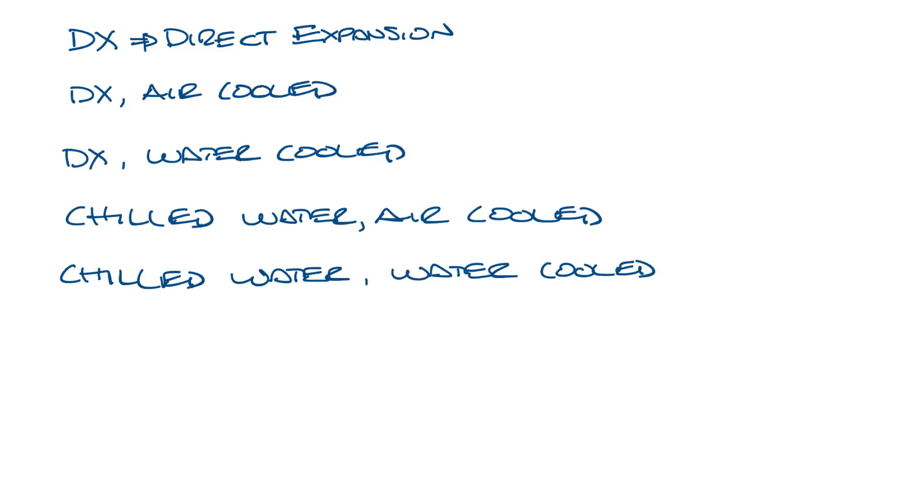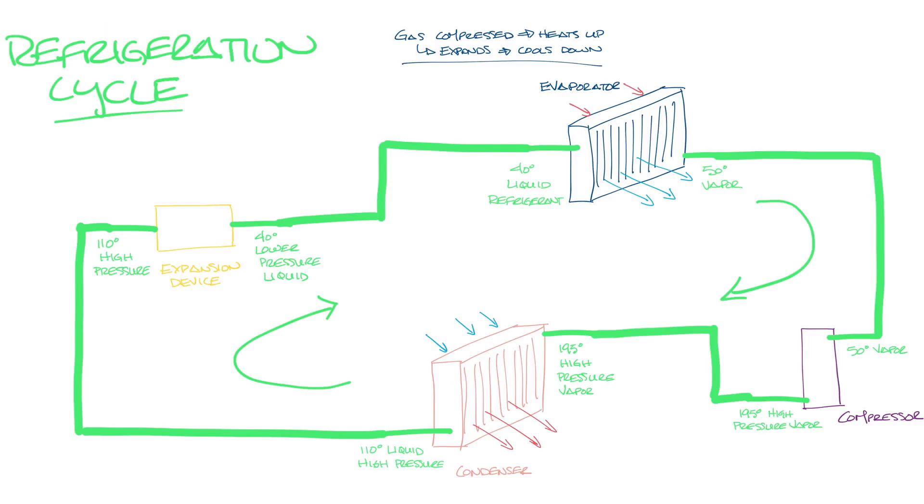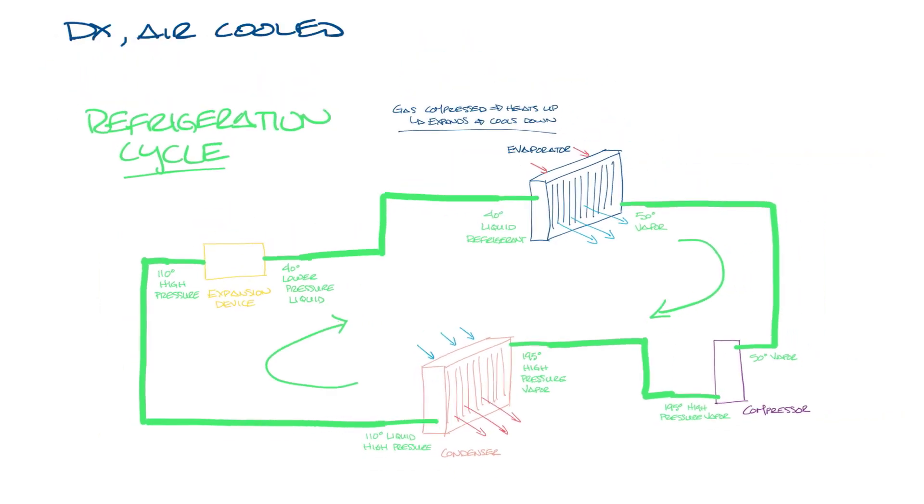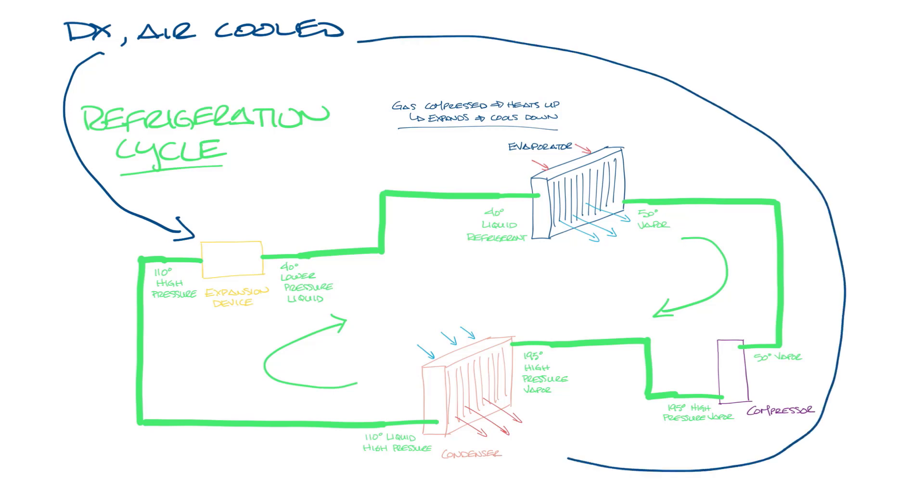So let's start with the DX air-cooled system. It's called direct expansion because we use the expansion compression of the refrigerant to produce cooling. And it's called air-cooled because we use a fan to draw air across the condenser to cool the refrigerant. It's basically what I drew in the last video, so let's pull this up here now. So here you can see, this is the DX part of it, and this is where it's air-cooled.